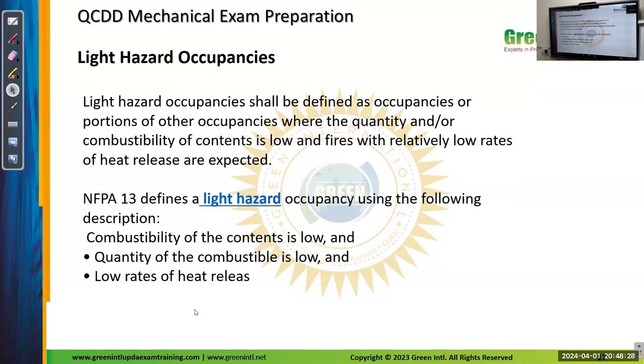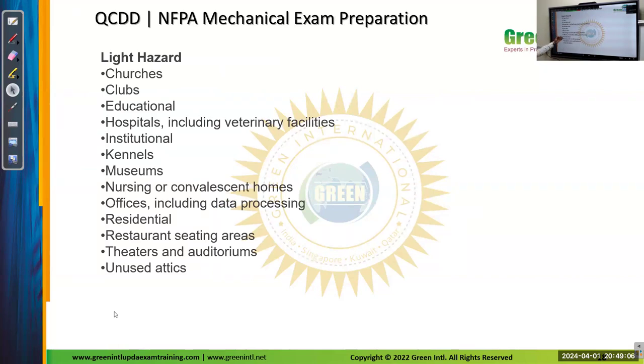Light hazard occupancies. We have seen this in many topics, but I am still reminding you. Light hazard occupancies shall be defined as occupancies or portions of other occupancies where the quantity and/or combustibility of contents is low and fires with relatively low rates of heat release are expected. So the main characteristic of the light hazard group is that it will not catch fire by itself. The combustibility of contents is low, the quantity is low, with low rates of heat release. These are the areas considered light hazard: churches, clubs, educational institutions, hospitals, institutions, museums, nursing and convalescent homes, offices, residential areas, restaurants, theaters, and unused attics.